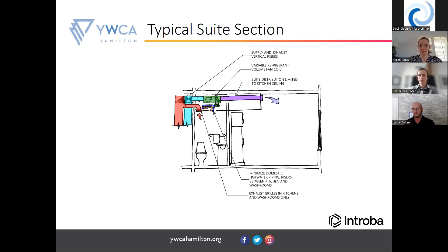On this project, in 2018, we researched air source heat pumps and looked into CO2 heat pumps at the time. They were newer technology, and in our cold weather application, I'm not going to say they were unproven, but they were deemed a bit more risky for the project at the time. It would also have been a single source for those types of units. So we ended up deciding to go with natural gas fired systems on this project, in concert with the design team. We wanted to make sure we were controlling first cost and risk to the project, because there were quite a few new things happening on this project.